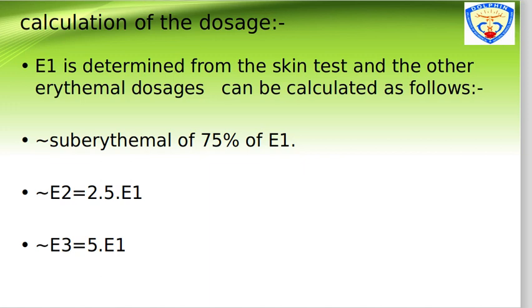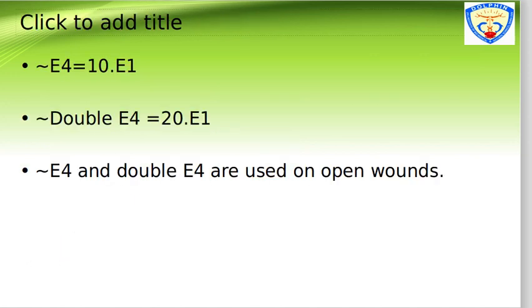For dose calculation: the MED (minimal erythema dose) is determined from a skin test, and other erythema doses are calculated from it. Suberythema dose is 75% of MED. E2 is 2.5 times MED, E3 is 5 times MED, E4 is 10 times MED, and double E4 is 20 times MED. E4 and double E4 are used on open wounds.